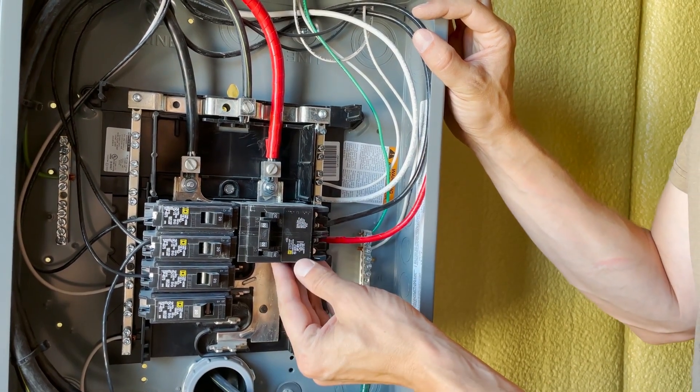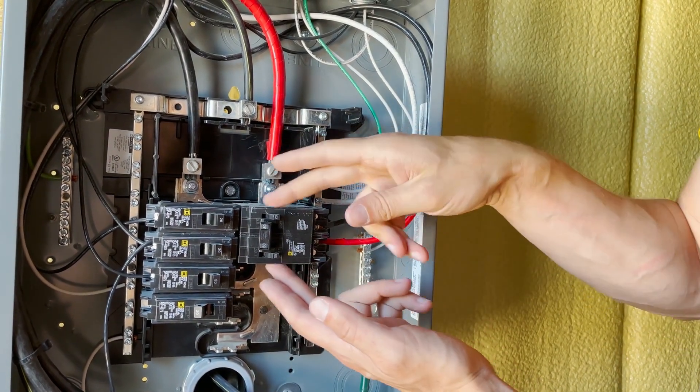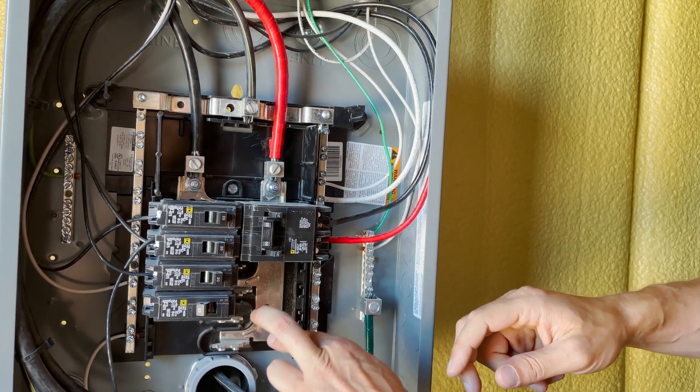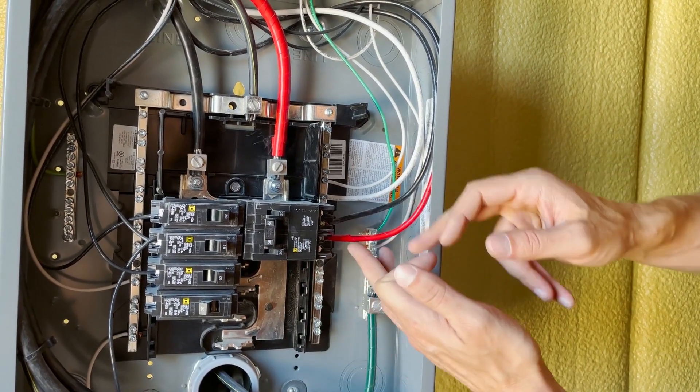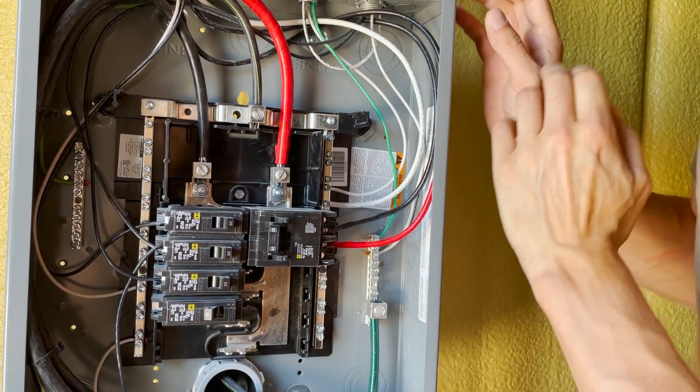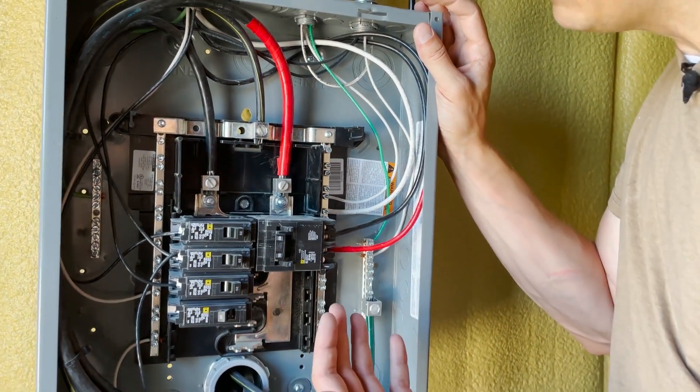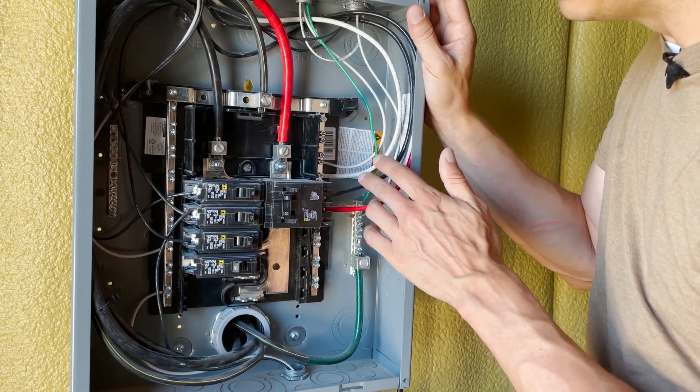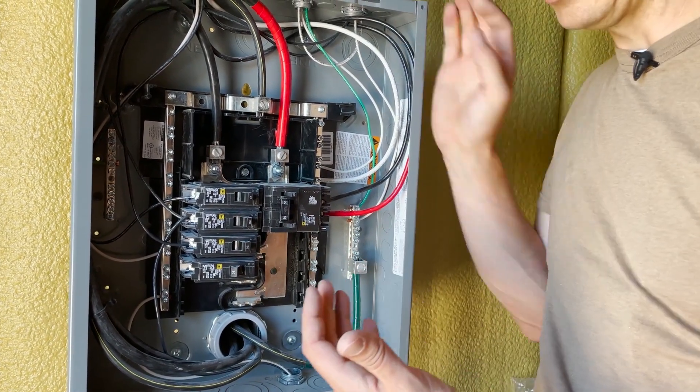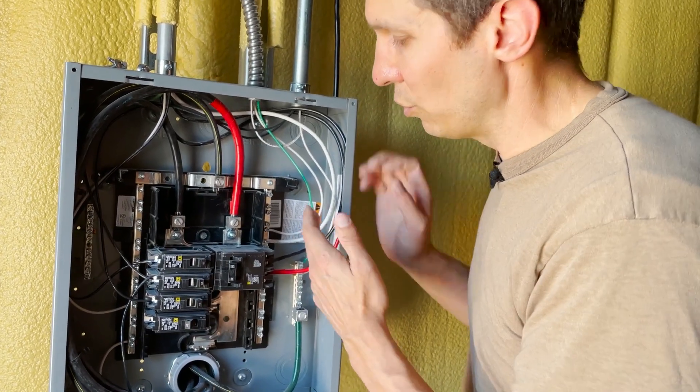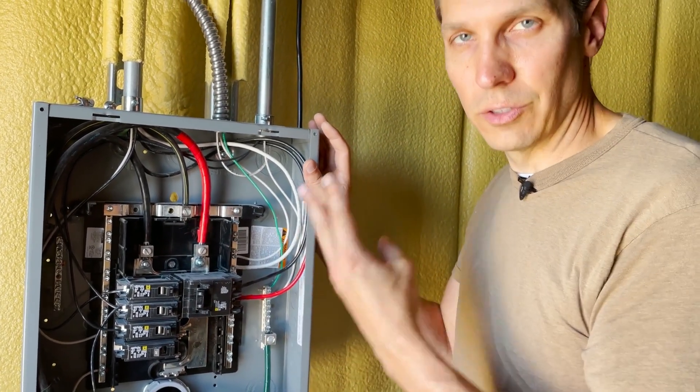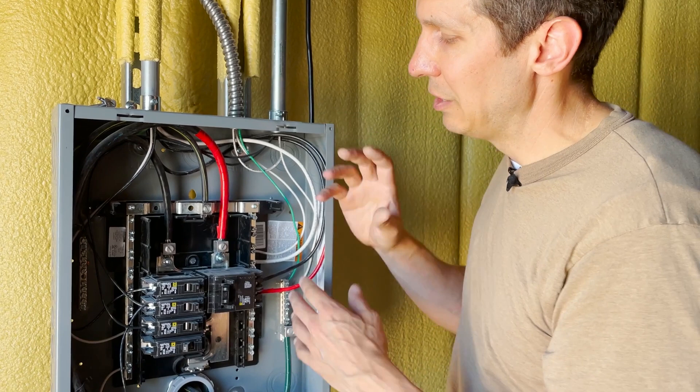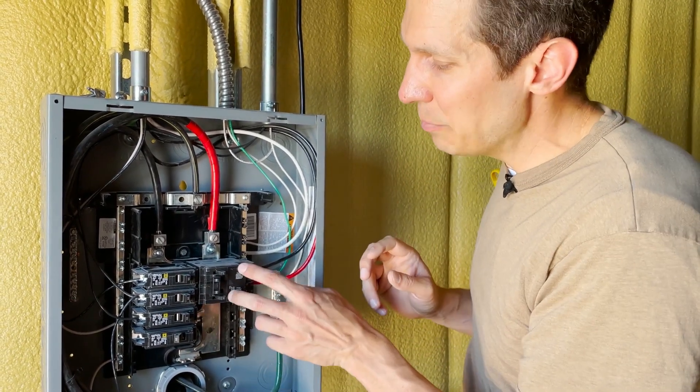If you have a 240-volt system that you need, you have to have a double breaker like this that can tag onto both of these lines. Then you put black into one and red into the other and run it to where you need to go. If you have a 240-volt outlet that doesn't need neutral, you'll only run these two and ground. But a lot of times, like on a dryer, it'll be black, red, neutral, and ground, so you'll need to run four wires—three conductors, one ground wire.